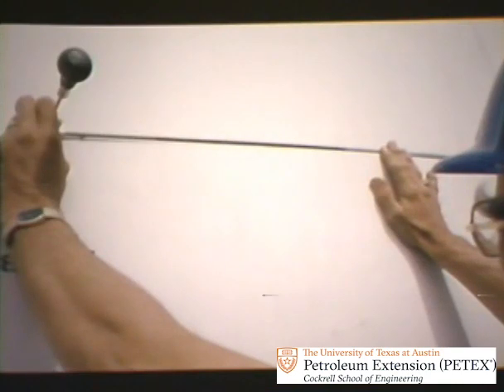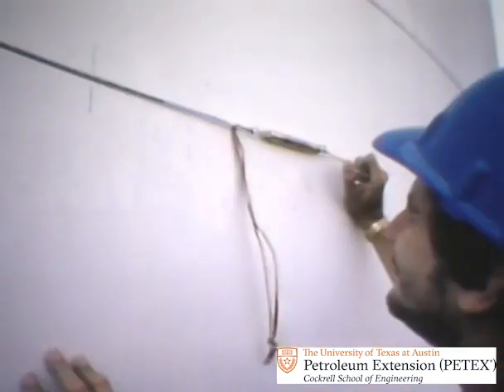The tape's then moved forward and anchored with its 0 reading on the 100-foot score. Tension is pulled, and the tape read where its reading contacts the original 0 vertical score. This reading is added to 100 feet to get the circumference of this ring with a 100-foot standard tape.